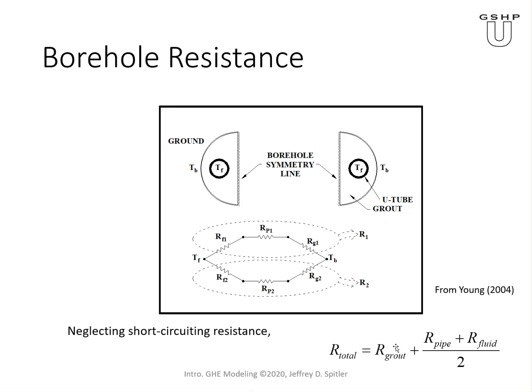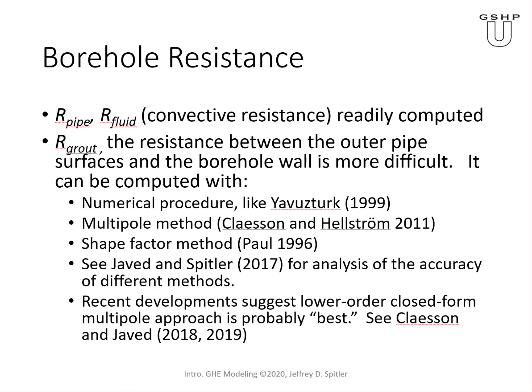This expression doesn't quite match this network exactly; if you connect the two grout paths as a single grout, then the expression matches the network. The resistance of the pipe and the convective resistance at the wall are easily computed if you know the convection coefficient — we usually use a correlation like the Dittus-Boelter correlation or similar for flow inside a pipe. The hard part is calculating the grout resistance, and we'll have a separate lecture on borehole resistance.